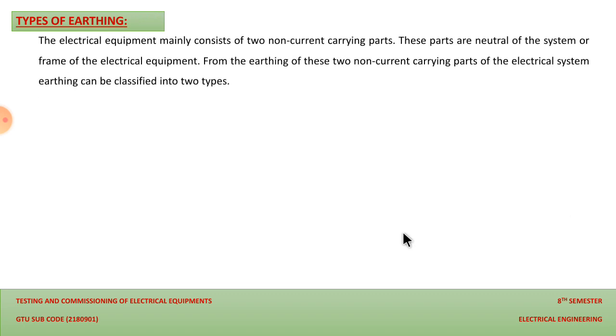The electrical equipment mainly consists of two non-current carrying parts. They are the neutral of the system and the frame. Through the neutral there is no current transfer, and the second portion of the instrument is its body, or we can say surface. From the earthing of these two non-current carrying parts of the electrical system, the earthing can be classified basically into two types, that we provide for the protection of the system and the human being working with it. First is neutral earthing, and the second is equipment earthing. Let us discuss both earthing in detail one by one.